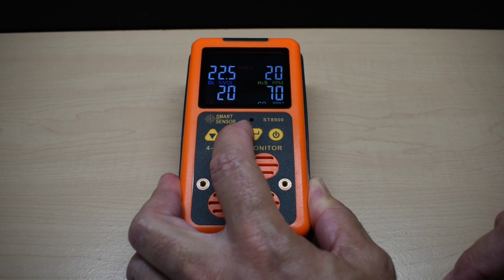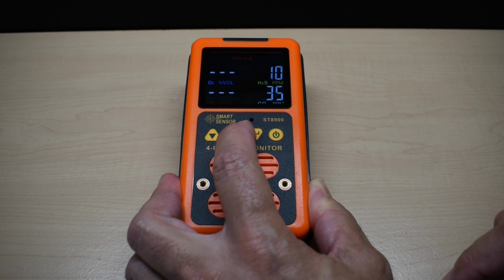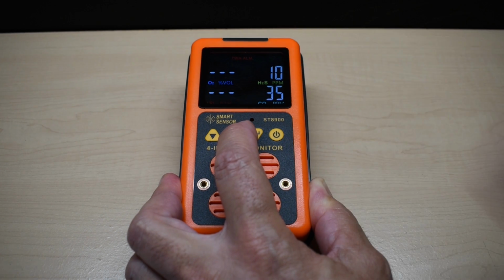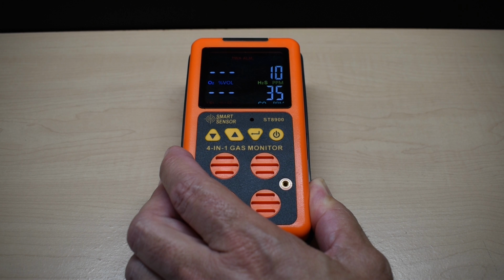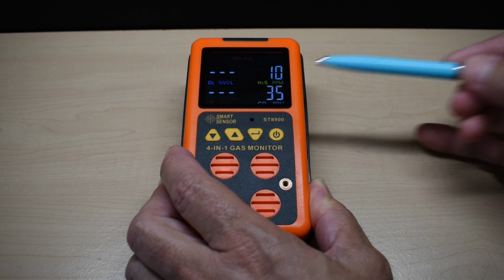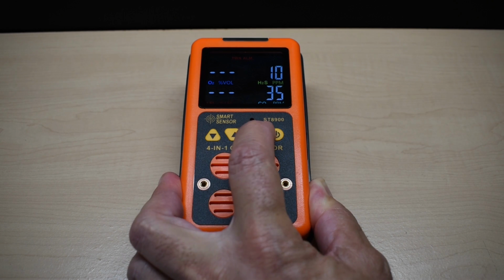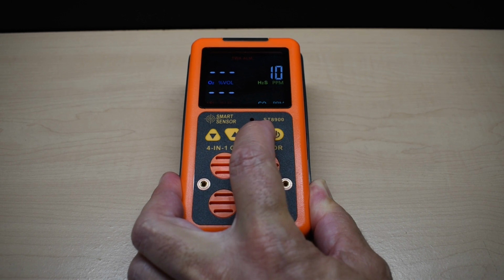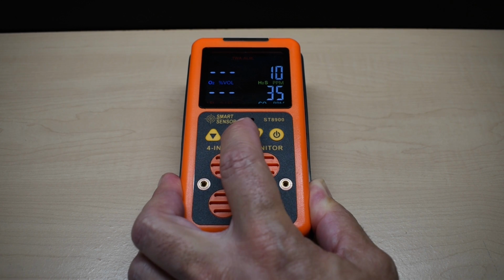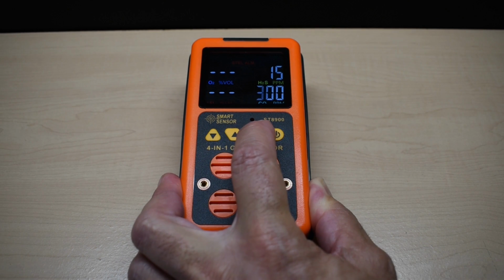And if I push this, now this is your TWA alarm, which is your time-weighted alarm. You can leave these settings as is, or you can also change those. The same thing applies for the short-term exposure limit. So if I push this, it should bring us there. Yep, same thing.